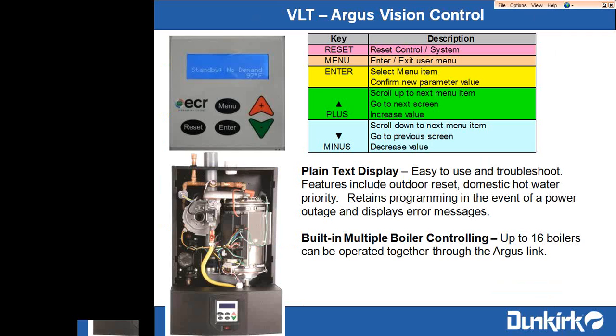The control that's on the boiler is a control called an Argus controller. Very simple, very easy for the contractor to get into. It provides a multitude of functions, probably more than most contractors will need out of the boiler. But the nice thing about it is it's all English text. No numbers, no letters, no codes. All in English. It tells them the operational status of the boiler, and if there's anything wrong, any sensors that may fail, or low water conditions, it'll all be spelled out basically.